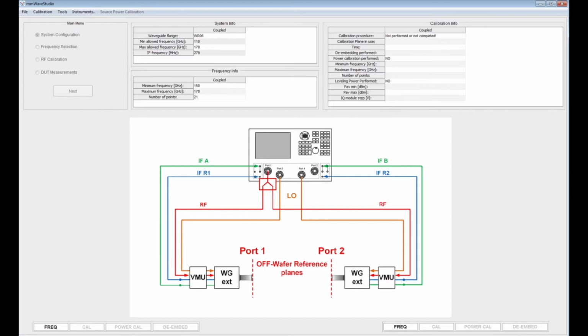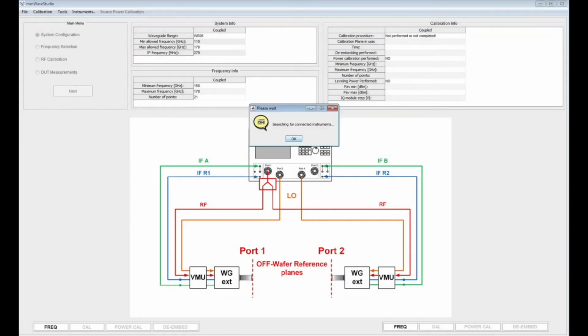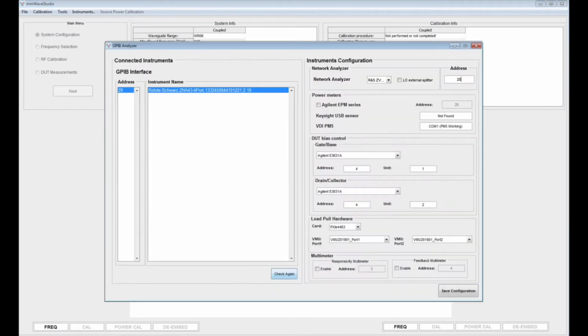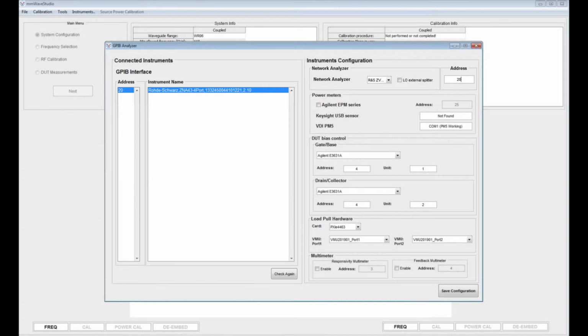Once the GPIB interface is configured, we need to scan for the instruments connected to our PC that will be used during the load pull measurement. For that, we go to Instruments, GPIB Serial Analyzer, and wait until the software automatically finds the connected instruments. When the GPIB Analyzer window opens, we can see that on the left-hand side we have a list of instruments that are connected to our GPIB interface.